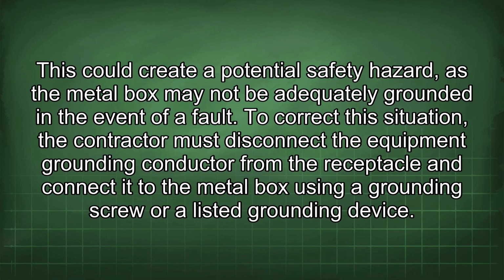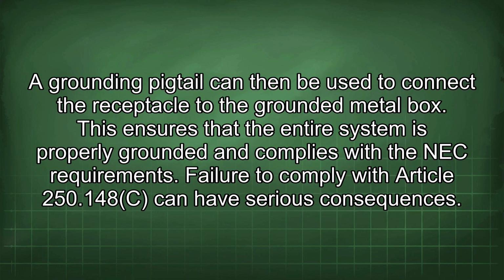To correct this situation, the contractor must disconnect the equipment grounding conductor from the receptacle and connect it to the metal box using a grounding screw or a listed grounding device. A grounding pigtail can then be used to connect the receptacle to the grounded metal box.